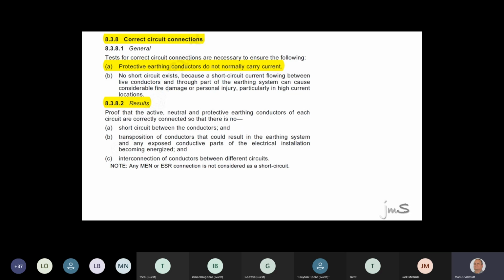You're breaking 8381A. And that is a fault, because this standard is cited in the regulation, and you shall comply with the standard. Right, guys? Have you guys ever heard about an impedance test? Only 2 more to go, and then we can have a smoke break. So, very important. What is an impedance test? When do we do an impedance test? Do we do it dead? Do we do it live?